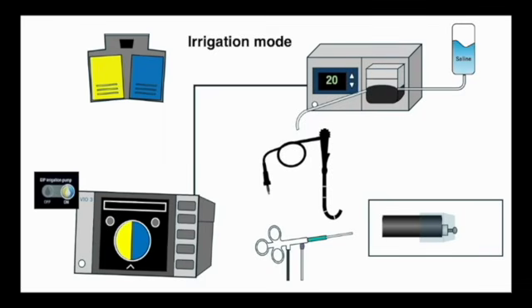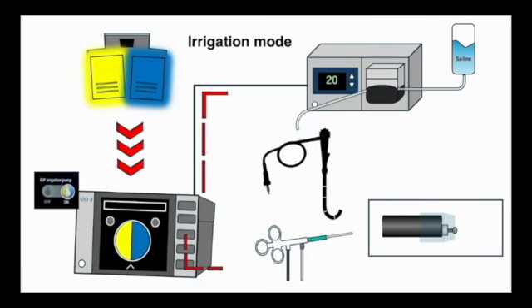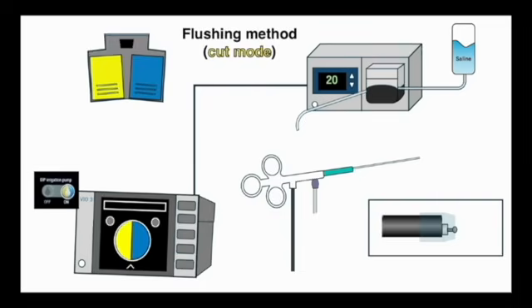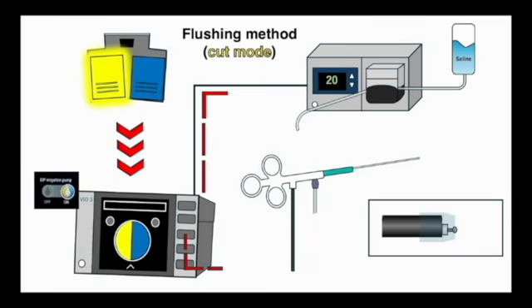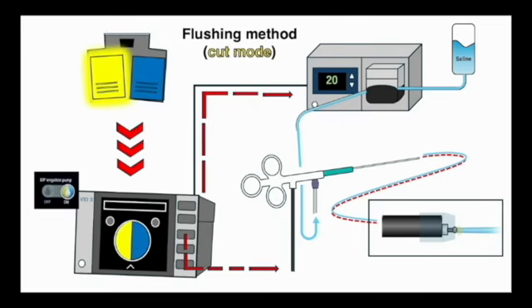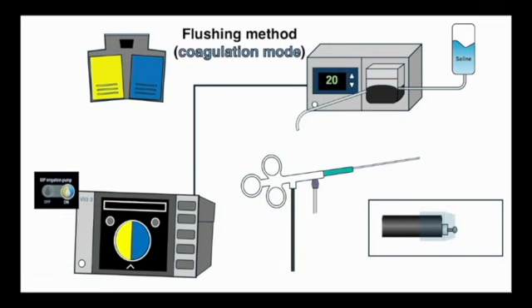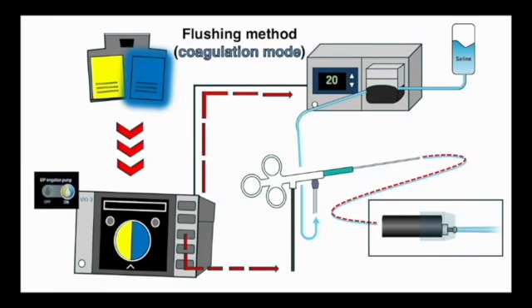To start, we will describe the irrigation setup. In the conventional irrigation mode, the pump is connected to both the endoscope and the electrosurgical unit. Pressing the electrocautery foot pedal initiates water flow through the endoscope channel while simultaneously activating electrical output. In contrast, in the flushing method, the irrigation pump is connected directly to the knife via extension tubing. Using the same interlocking system with the electrosurgical unit, stepping on either the cut or coagulation pedal simultaneously activates both electrical output and saline flushing. However, now the saline is ejected from the base of the knife instead of the endoscope. This small difference is key in changing the effects of the electrical output on the tissue.